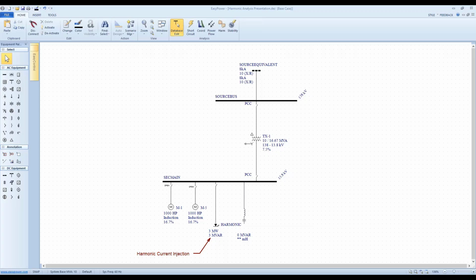In terms of harmonic issues, what I have seen is that harmonics tend not to be a problem until some type of capacitors are installed. It's almost always the capacitor banks within facilities, in my experience, that cause problems. Most facilities can handle a significant amount of harmonics without issue until the day a capacitor bank is installed, and it's that resonant condition that really exacerbates any harmonic issue within the plant.